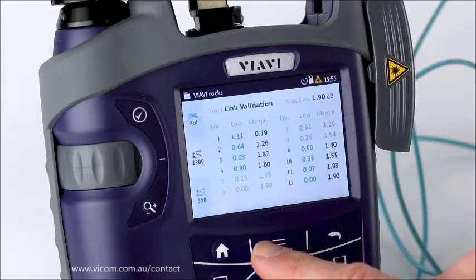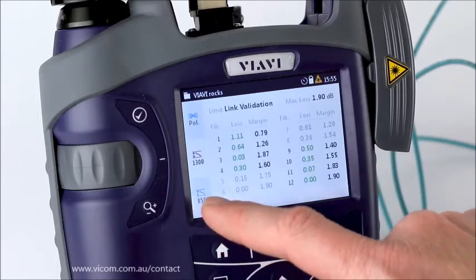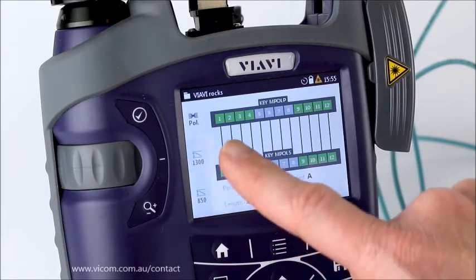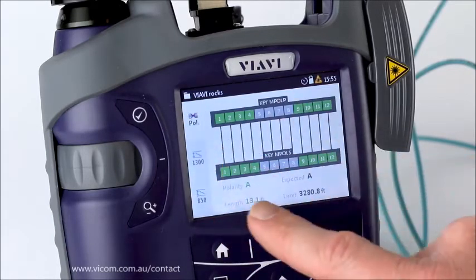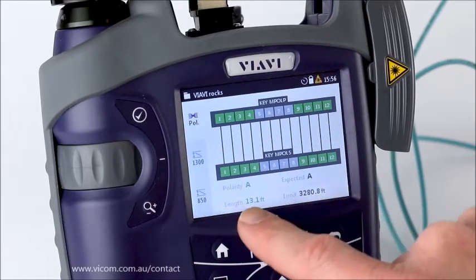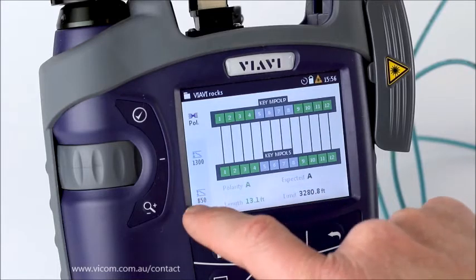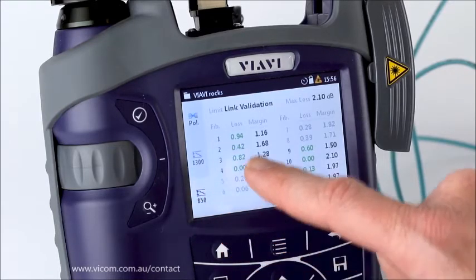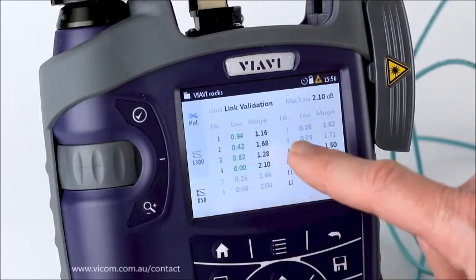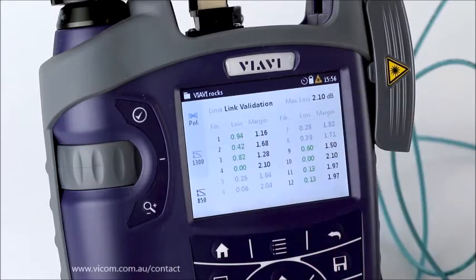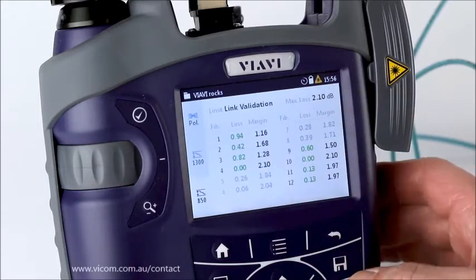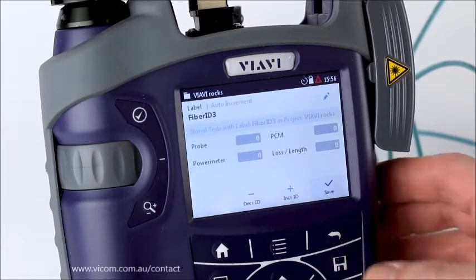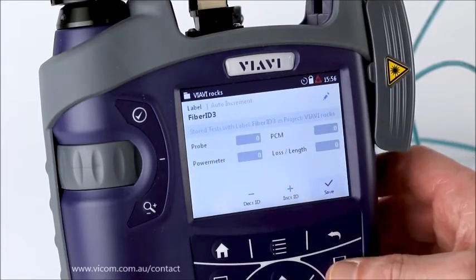I can choose to go into a detailed view where I can look at different elements. Starting at the top, I see polarity — it's polarity A, and it was expected A. Then the length and the length limit. Looking at 850nm, I can see each individual fiber, what its loss was, and what its margin was. In the top right I've got what the max losses are.